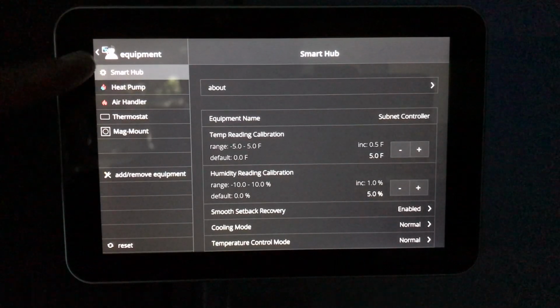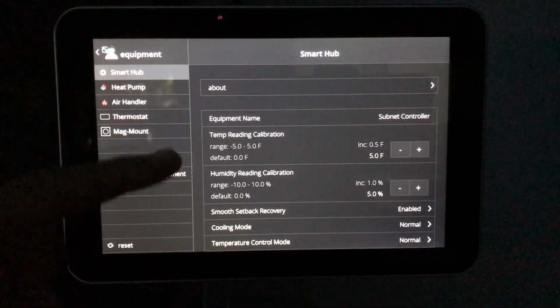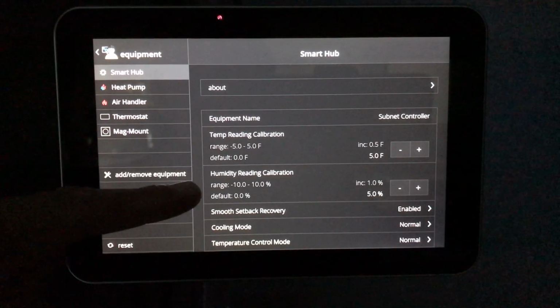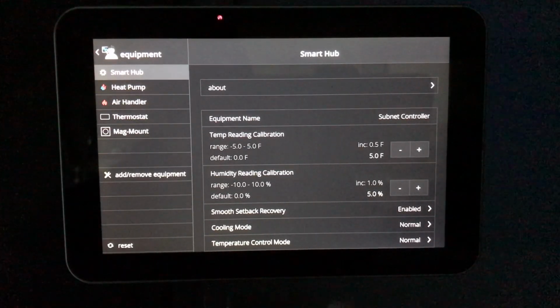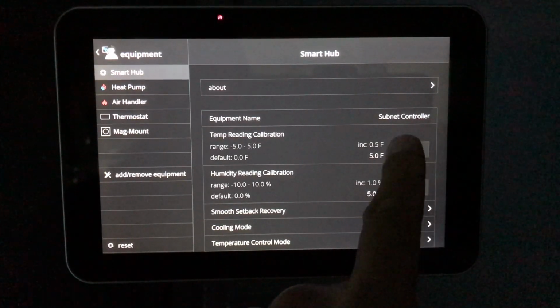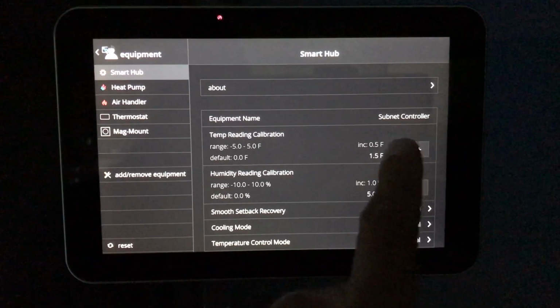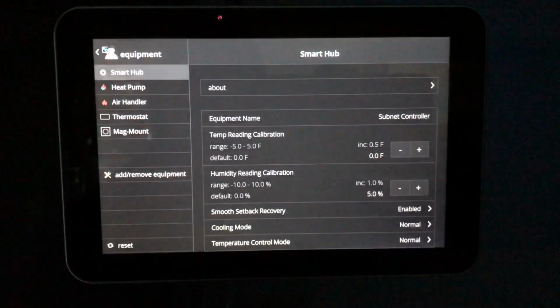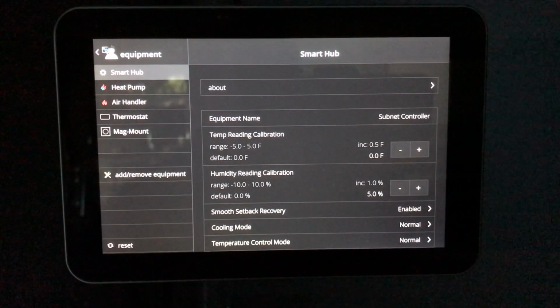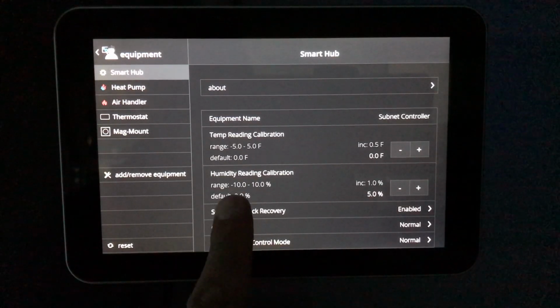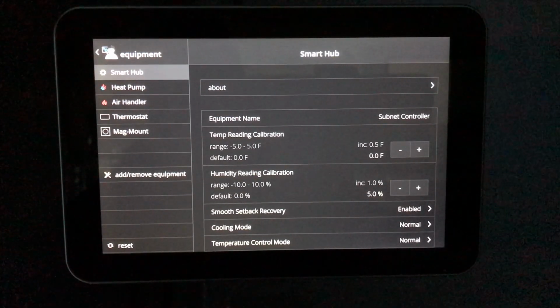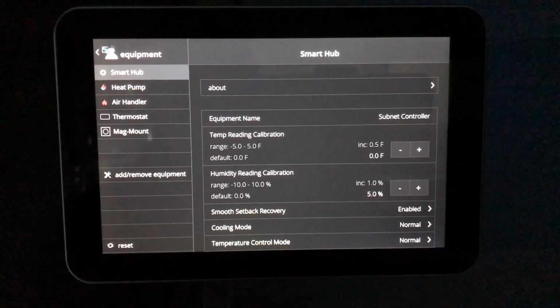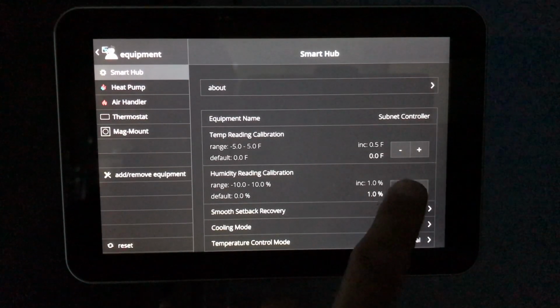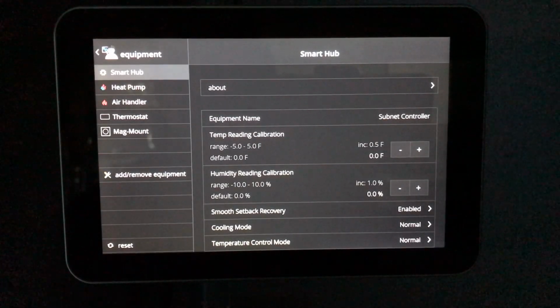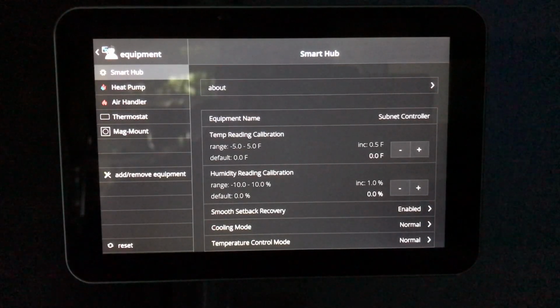Now right here, right where you default going into the menu, is where it opens up into temperature reading calibration and humidity reading calibration. And right now I've got it changed to +5. So let's go ahead and put it right back at 0. It moves in increments of ½ degrees, and it will only give you the range of plus or minus 5 on the temperature setting. But on humidity, we have either negative or plus 10% on the humidity setting. Right now it's at 5% above. Let's go ahead and change that back to 0. And this is where the thermostat comes out of the factory, set at default.